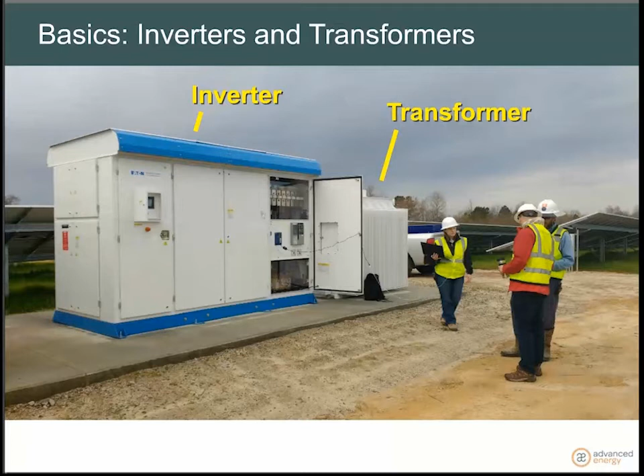Finally, we need to connect the AC power from the transformer to the electric grid. That generally requires a series of switches, meters, and safety devices to allow the facility to be connected and disconnected, monitored, and protected from power faults—very similar, if not the same, as the equipment used on the grid itself.